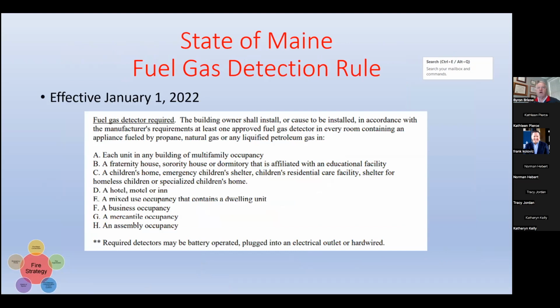In the state of Maine, you have a unique rule. I think New York City is putting one in similar to this, but based on an incident that occurred in your state, I believe in 2021, there's now a fuel gas detection requirement. If you have a combustible gas being used in a facility, flammable gas being used in a facility, you have an obligation to have a gas detector in that building.